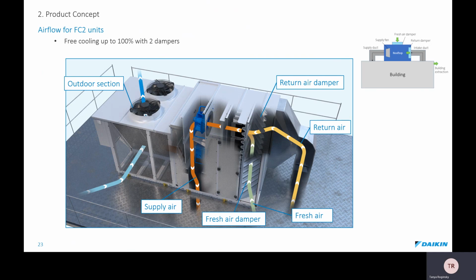The 2 dampers always work in a synchronized way. For example, if the fresh air damper is open 30%, your return air damper will be open 70%. When adding fresh air, you have to provide local extraction to prevent overpressure inside the building. The fresh air integration can be managed in a fixed way, with a fixed damper opening, or in a proportional way, controlled by a Daikin CO2 sensor. We can also offer free cooling operation, and this can be achieved when the outdoor temperature is lower than the indoor temperature, and there is an actual demand for cooling.